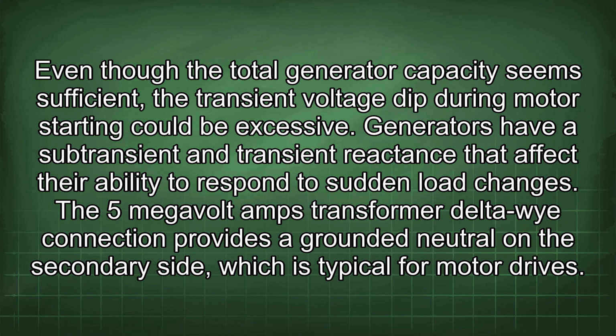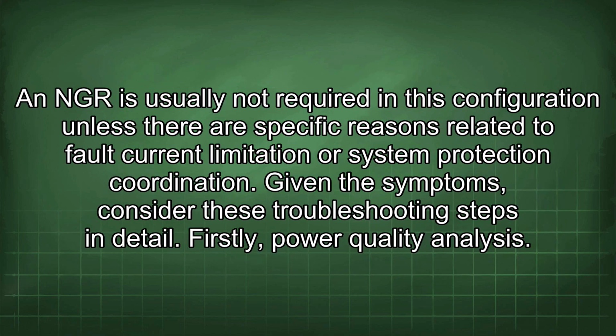Generators have a subtransient and transient reactance that affect their ability to respond to sudden load changes. The 5 megavolt-amp transformer delta-Y connection provides a grounded neutral on the secondary side, which is typical for motor drives. An NGR is usually not required in this configuration unless there are specific reasons related to fault current limitation or system protection coordination. Given the symptoms, consider these troubleshooting steps in detail.